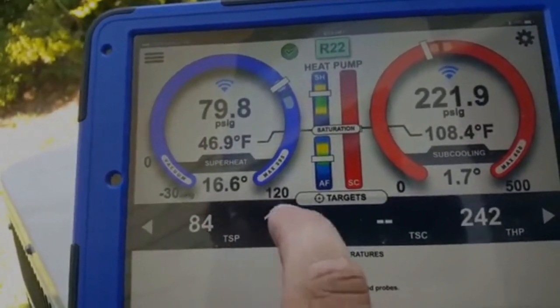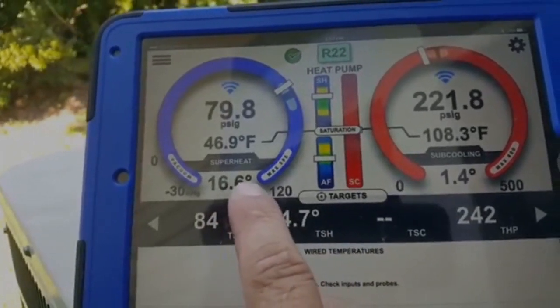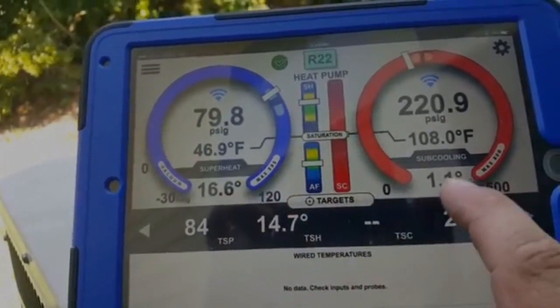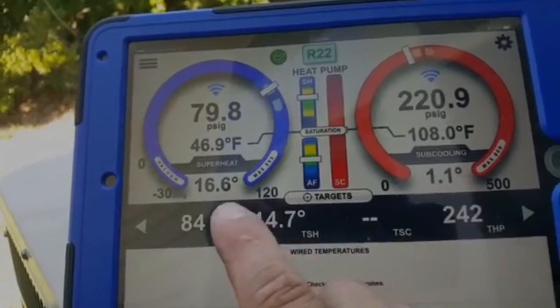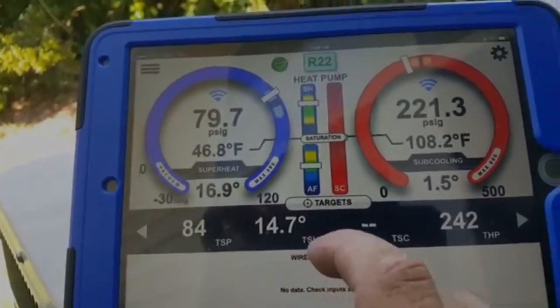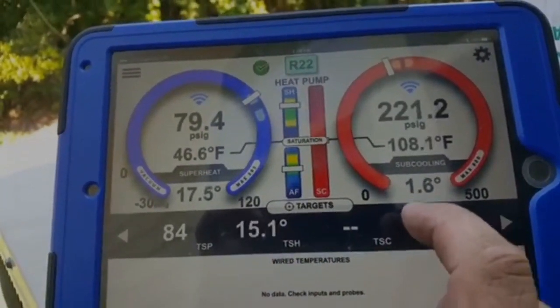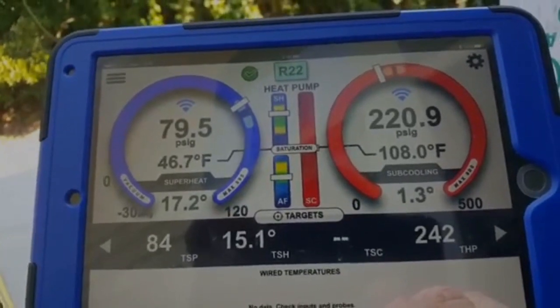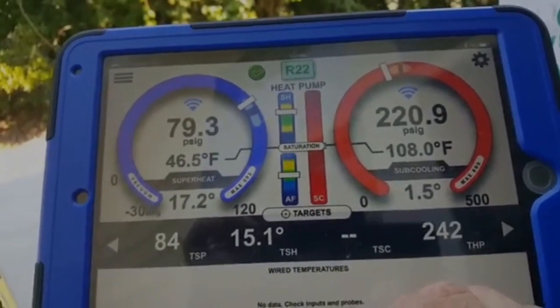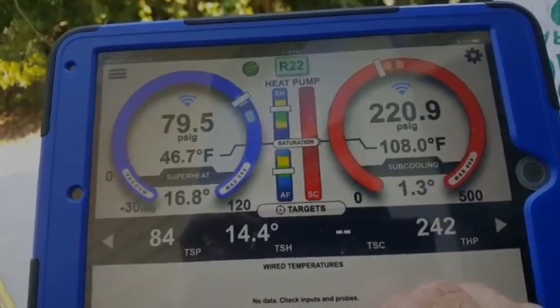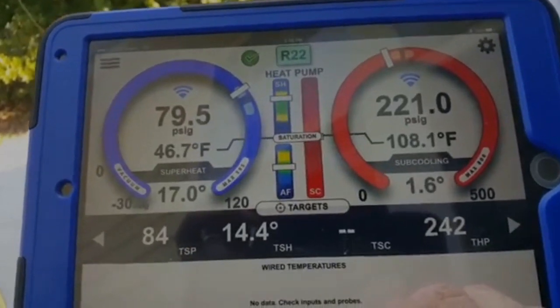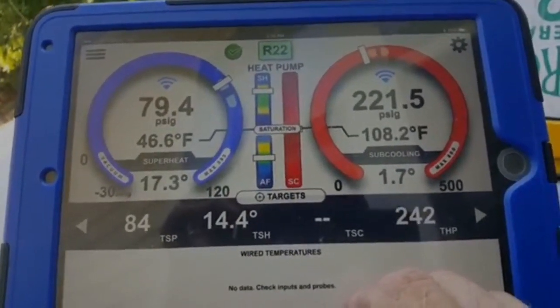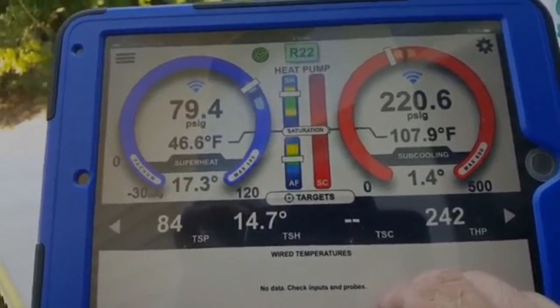If we took it down to try to get a little bit closer, that'll end up bottoming out because of the piston size, and this number will still be too small, so I might as well keep a little bit of superheat on it so we're not just flooding it back trying to get a little bit of subcooling. Because we'll get subcooling out of the unit, but the evaporator will be kind of flooded by the time you get enough in there to where you normally see it like 5, 6, 7, 8 degrees. So we're gonna leave it like that.